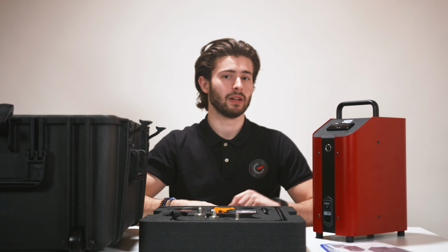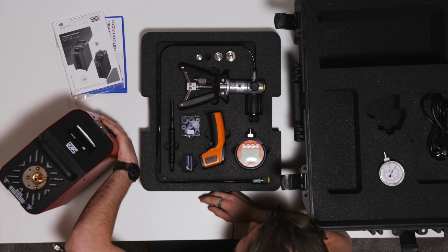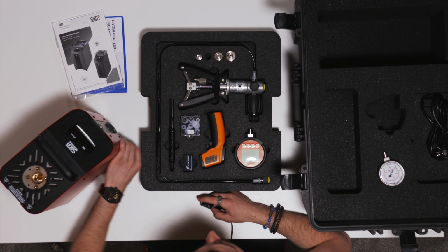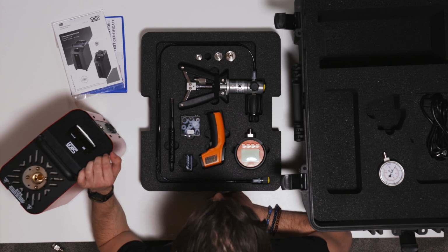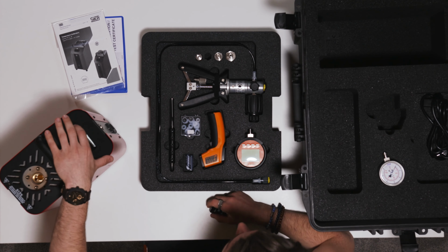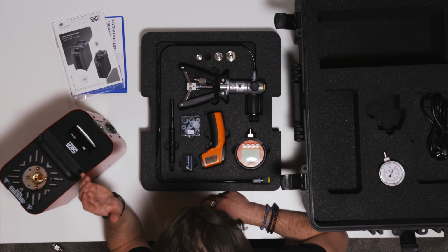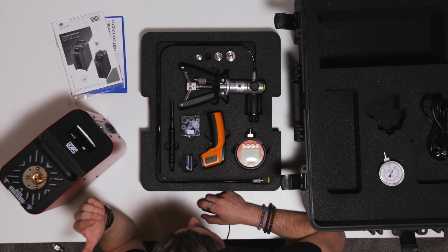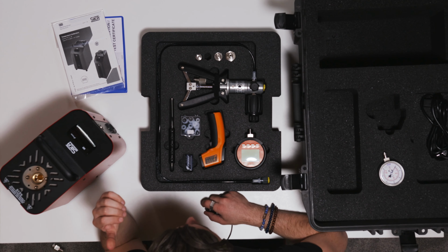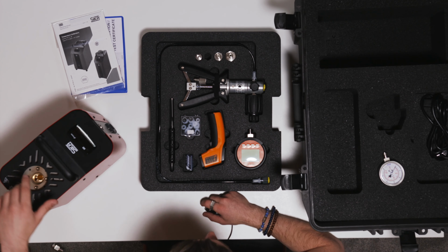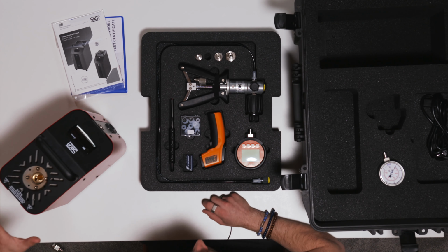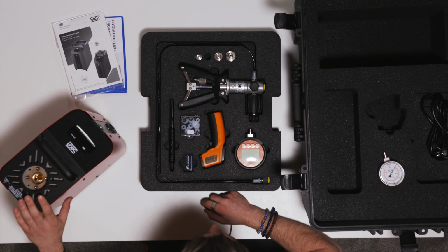For the temperature, the calibration block has to be plugged in, of course, at the front here and then turned on. And then you bring it up to temperature by setting the temperature with the buttons at the screen over here. The screen will show the setting temperature and the current temperature, and then after setting, it's important to already put the product that's going to be tested into the calibration block when you're heating it up, so that it will warm up with the block calibrator.